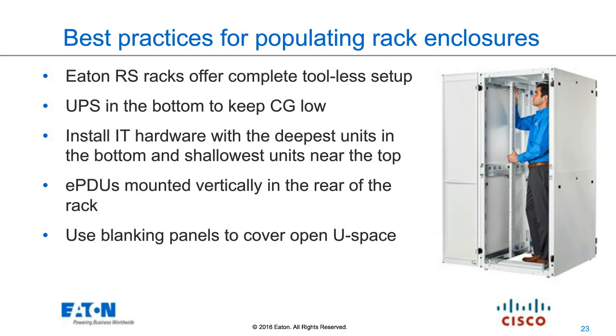Another consideration—I don't know if this is industry standard, it's my own personal preference—is to put the deeper devices in the bottom and the shallower devices on top. As warm air comes out of the back of your IT equipment, it tends to rise, since warm air is lighter than cool air. By tiering your equipment this way, you leave a larger void of air higher in the rack so that rising warm air has somewhere to go.